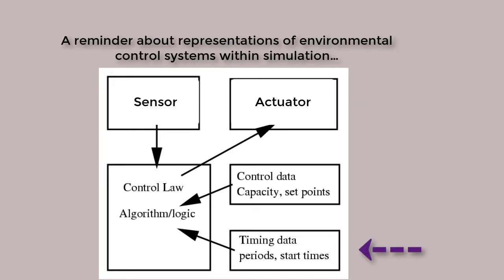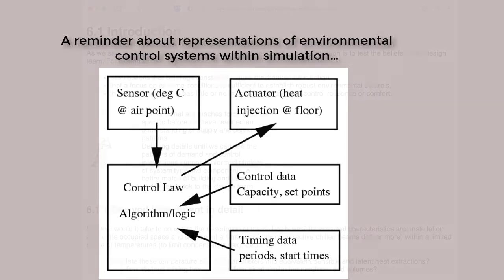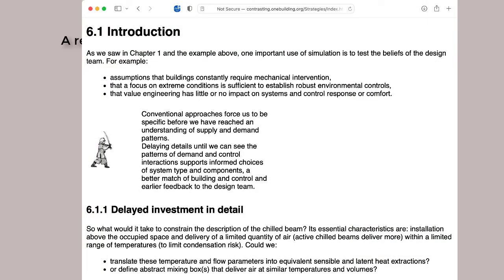Also on the graph is a schedule, and we take that from the definition of the office hours and set points. Let's say we want to maintain 15 degrees overnight and 20 degrees during office hours on weekdays, reduced hours on Saturday, maybe just frost protection on Sundays, and for cooling the set point, say 26 degrees overnight and maybe 24 degrees during office hours, with a setback on Saturdays, Sundays, and holidays.